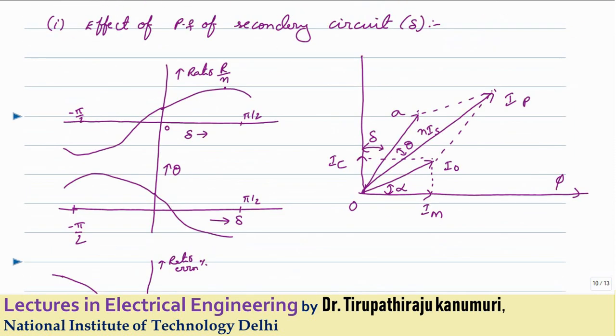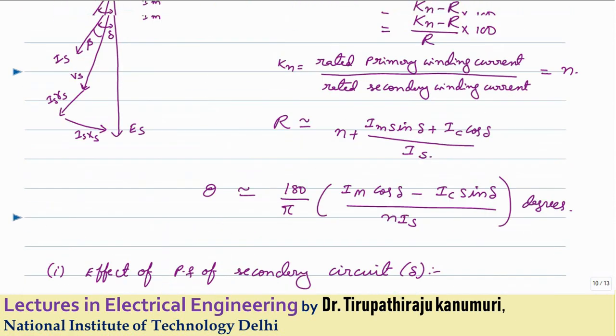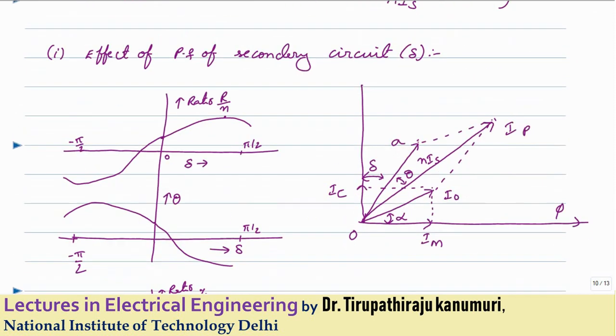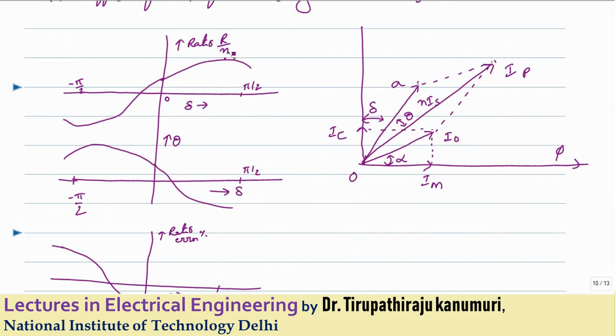Let us see the effect of the power factor of the secondary circuit on these errors. In the phasor diagram, I₀ is one vector and N×I_S is the secondary current referred to the primary side. Delta is the angle between I_S and E_S. We will examine how ratio error and phase angle error change as delta varies, while keeping N×I_S and I₀ constant. The transformation ratio R divided by N is first calculated; ratio error will be opposite to that since ratio error equals (N − R) divided by R.